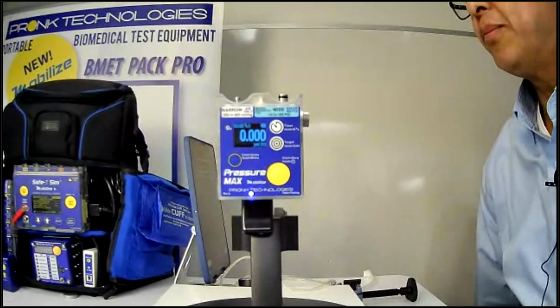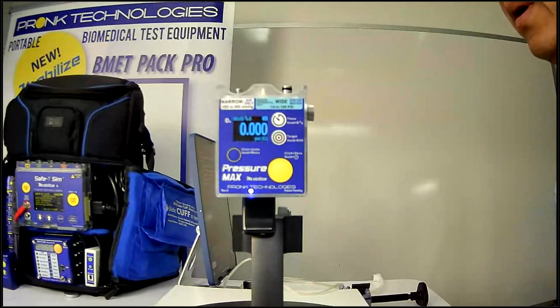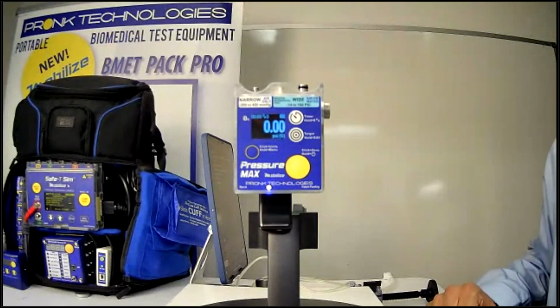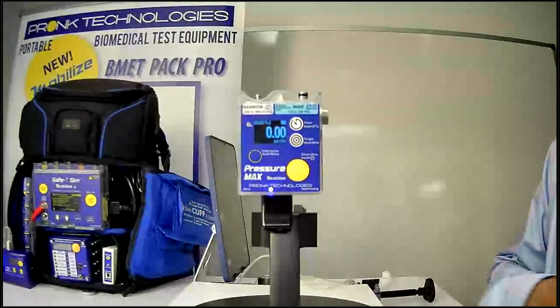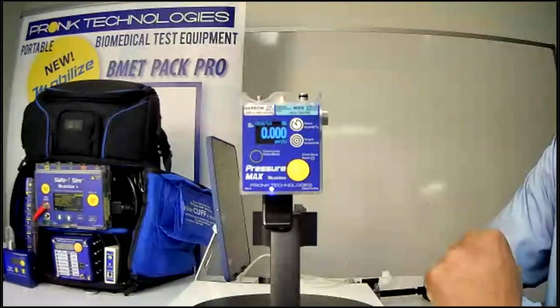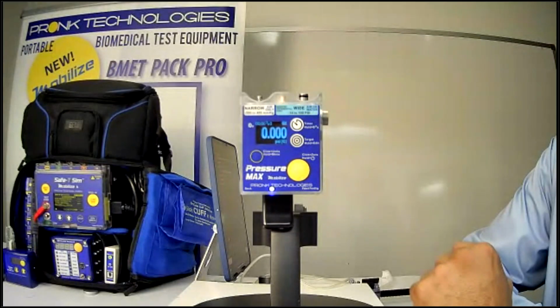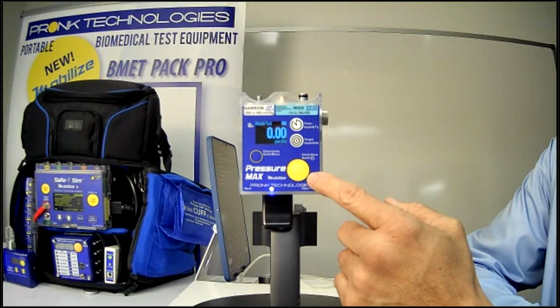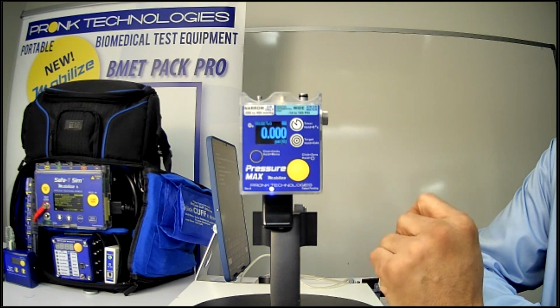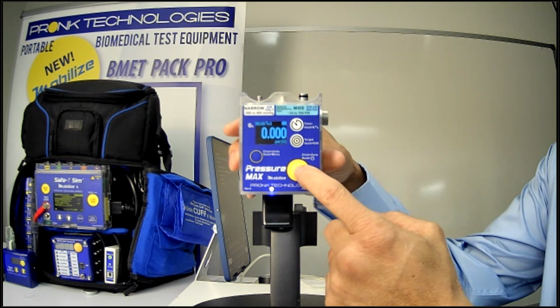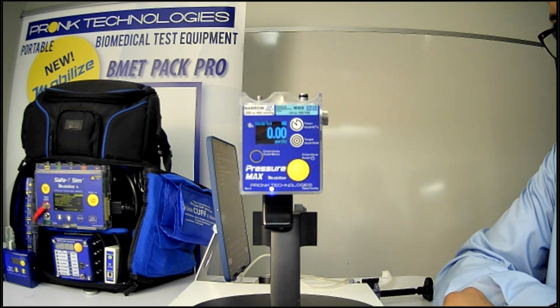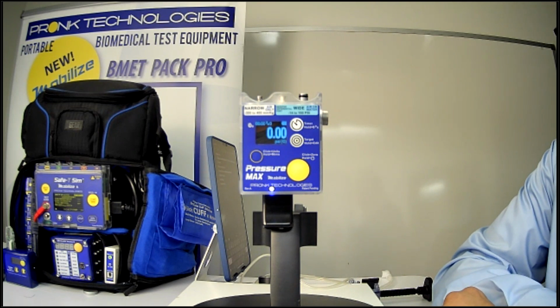So we're going to get a little comfortable here and talk about what it's capable of. Just a quick overview here of the screen and the overview of the unit itself. You see here you have the yellow button, which is the power on, power off the unit. It's also utilized to zero the pressure transducer. So if you simply tap on it, you can zero out the pressure transducer.